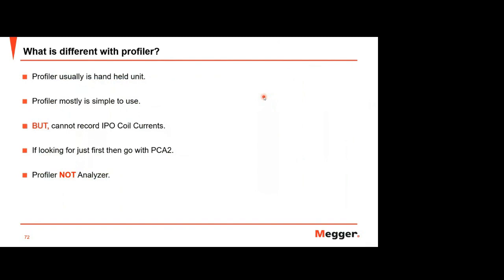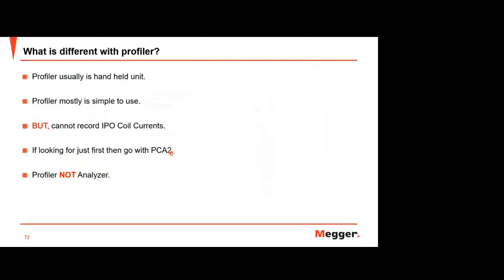The difference is the profiler can normally only measure one coil, so you cannot record the IPO coil current if there are many coils or three phases. Sorry, this is our old product. This is similar to a profiler, but not an analyzer, because an analyzer is more or less applicable for all circuit breakers, including the three phase IPO circuit breaker.